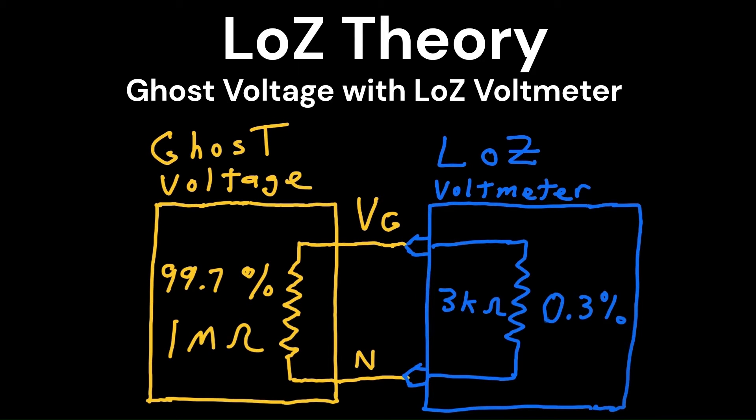However, low Z brings things into light. The low input resistance, typically around 3000 ohms, of the low Z mode puts a load on the circuit, letting you know that you have a problem.